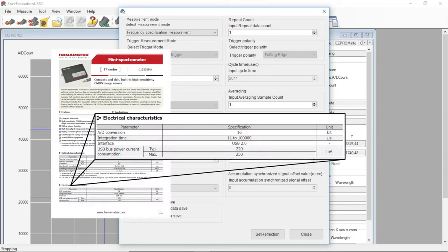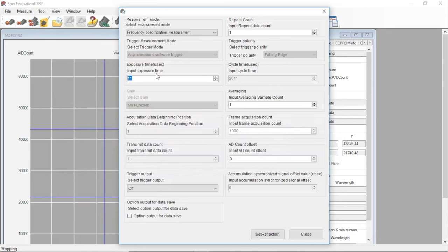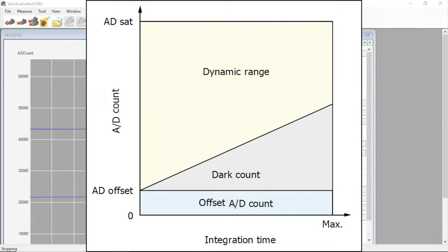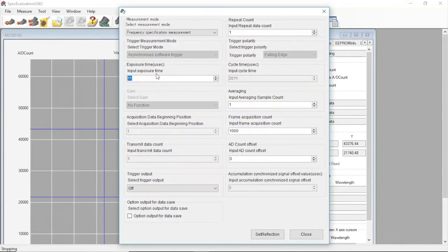For the C13555MA, this is 11 microseconds and the maximum integration time available is 100 milliseconds. As shown in the figure, while increasing integration time increases throughput, it also results in higher dark A to D counts. If you can afford higher dark A to D counts, longer integration times may be suitable for you. Just keep in mind, as well, that longer integration times equate to overall longer measurement periods.